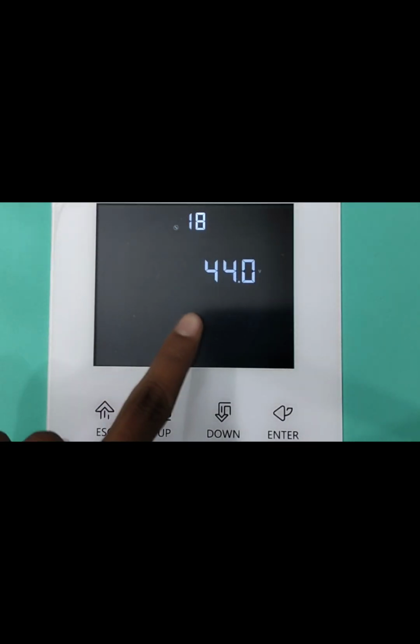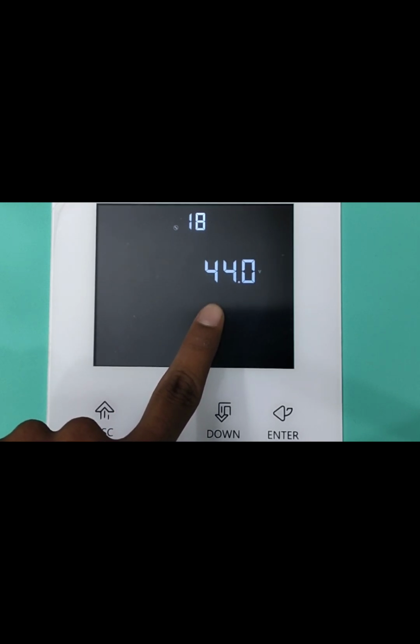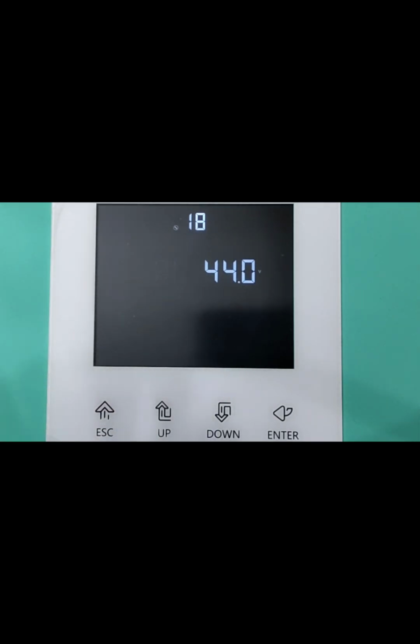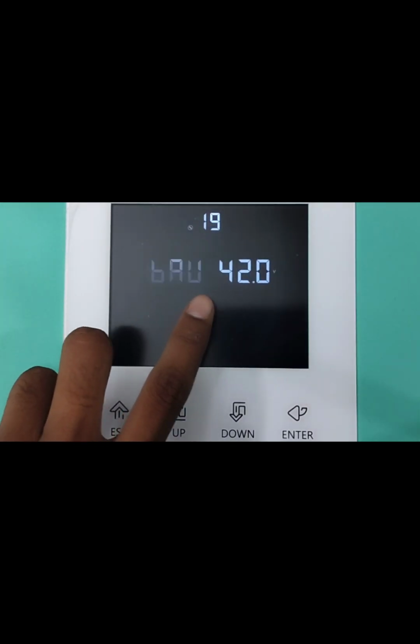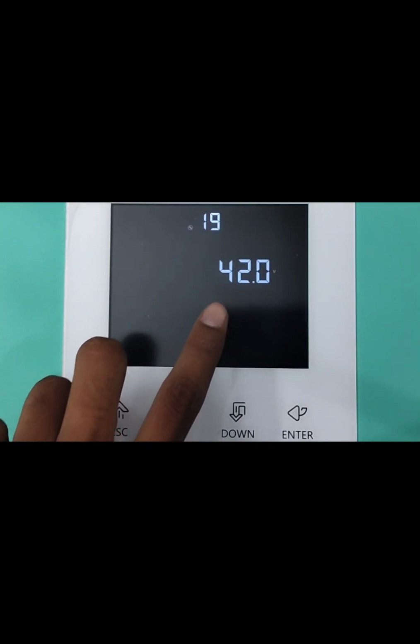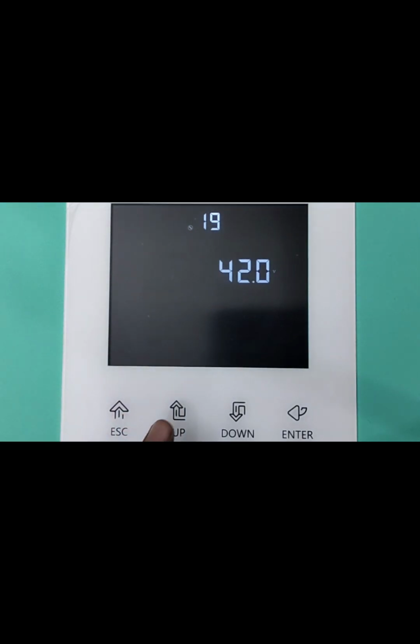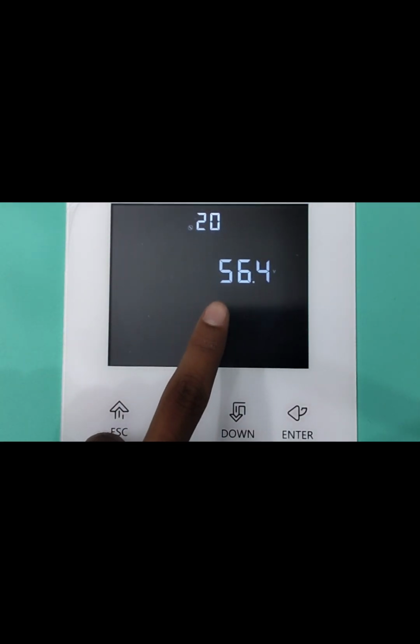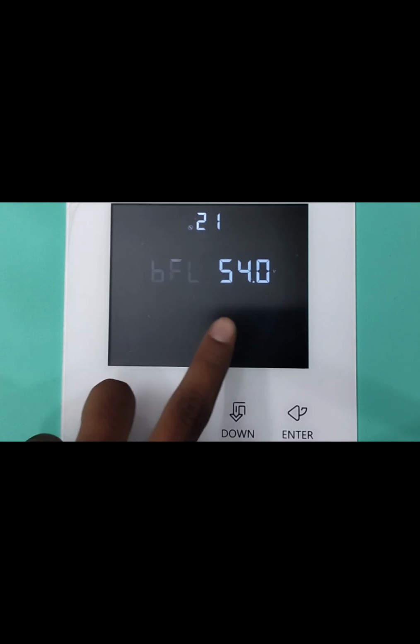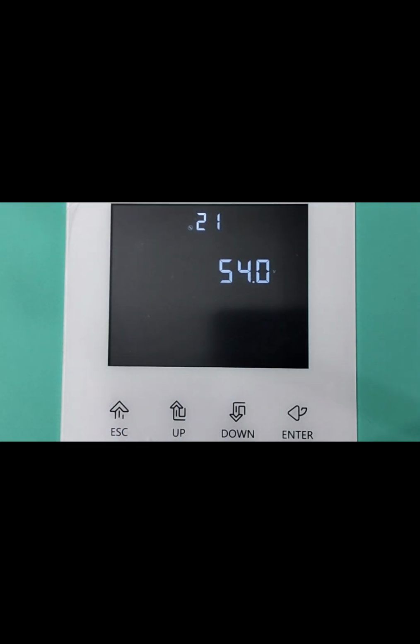Option 18. Here you can set battery low voltage, at which point the alarm will be generated. Option 19. Here you can set battery low voltage, battery cutoff. Option 20. Here you can set bulk charging voltage, but this voltage you can adjust if you will set battery type at custom. Option 21. Battery float voltage, which you can set according to your battery, and if you will set battery type at custom, then you can easily adjust this.